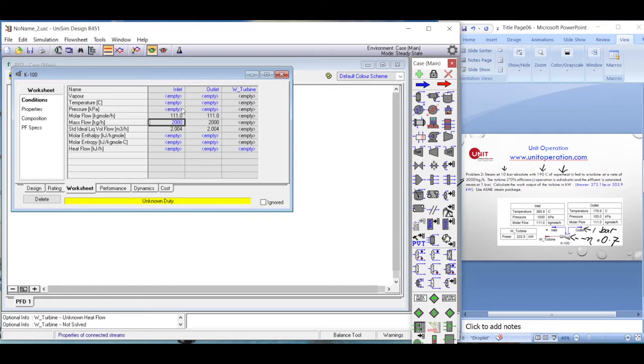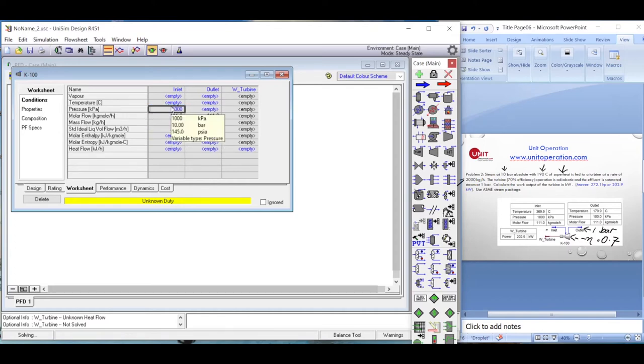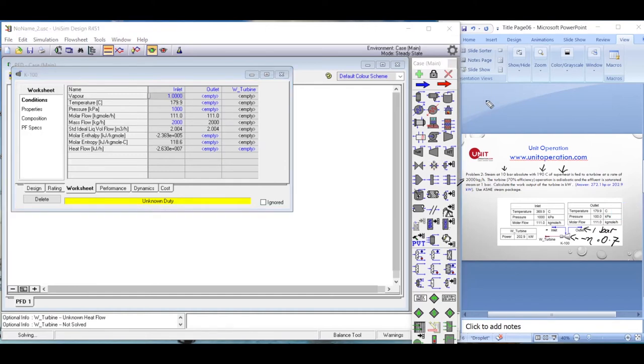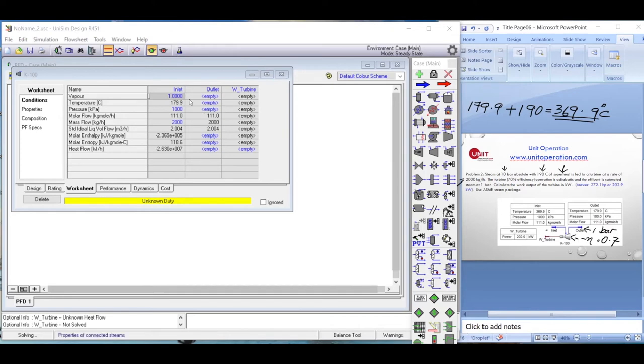For superheated steam, we need the saturation temperature at 10 bar and then add the degree of superheat. We enter 10 bar pressure and set the vapor fraction to 1, which gives us the saturation temperature. The saturation temperature of steam at 10 bar (1000 kilopascal) is 179.9 degrees Celsius. Adding the 190 degrees Celsius of superheat gives an actual inlet temperature of 369.9 degrees Celsius.